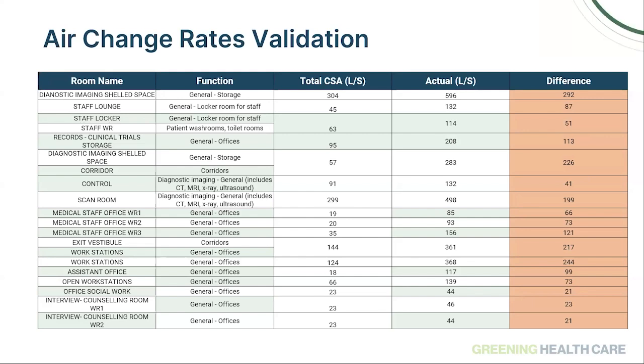Yeah, this was one where we figured out through this process that we were over-ventilating a lot of these spaces, often offices, locker rooms, things like that. They seemed over-designed, but we were able to still maintain the minimum airflow while allowing the cooling aspect to come back down, which resulted in savings too. That was done on a lot of the units.